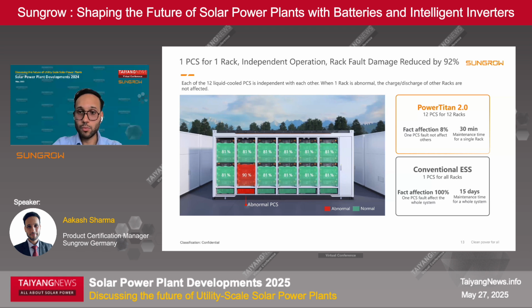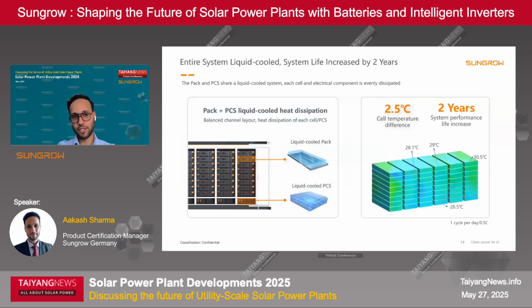Now moving on to the second aspect: PowerTitan 2 has a liquid cooled system, leading to increased system life. How does that work? Both the battery pack and the PCS are liquid cooled, meaning heat is evenly dissipated at the cell level and the PCS level. We've observed that the cell temperature difference is less than 2.5 degrees, which leads to an increase in system performance life by approximately 2 years.